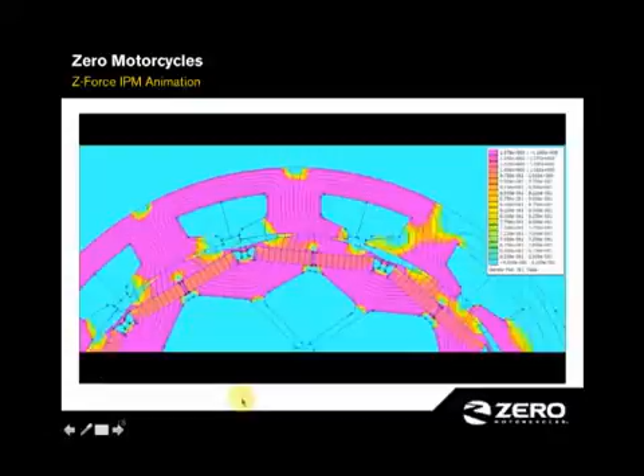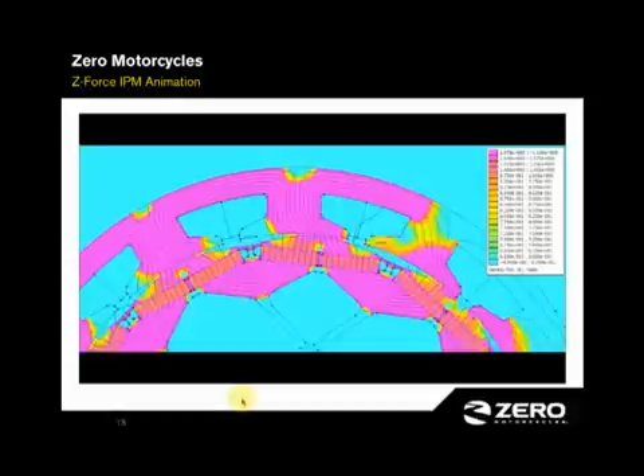That allows you to have a higher continuous output power, but also allows you to operate the motor at higher temperature, because the magnets are not producing heat. So you don't need to be so cautious about overheating the magnets related to the temperature difference between the stator and the rotor magnets.